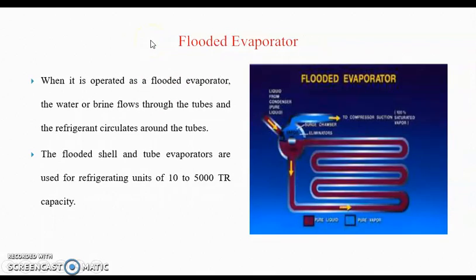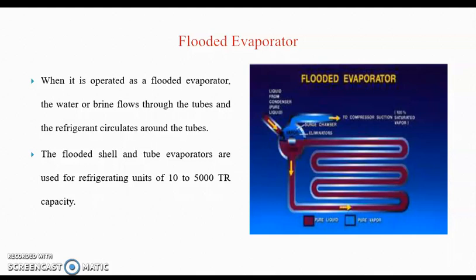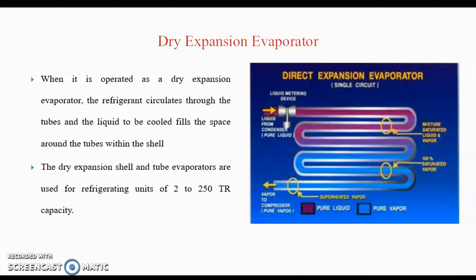The last type is the flooded type shell and tube evaporator. In the flooded type evaporator, the water or brine flows through the tubes and the refrigerant circulates around the tubes inside the shell. The flooded shell and tube type evaporator is used for refrigerant units from 10 to 5,000 tons of capacity, whereas the dry expansion type handles only 2 to 250 tons capacity.